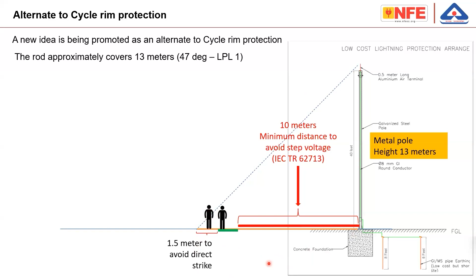So 10 meters, the red dot is the metal pipe. 10 meters from the metal pipe is unprotected. You will have touch and step potentials. Finally, the area which you are going to get in order to protect people is the green circle. If you are going to the red area, that means closer to the pipe, you will get hurt due to touch and step potentials. In the orange area, you may be exposed because you are taller than the protection angle. You may be getting hurt.